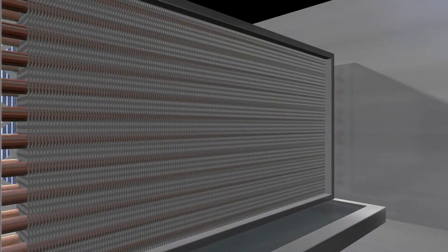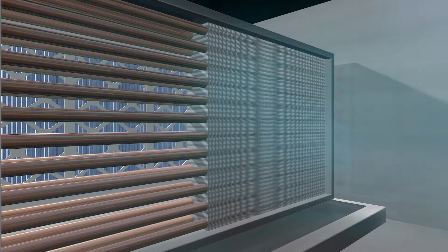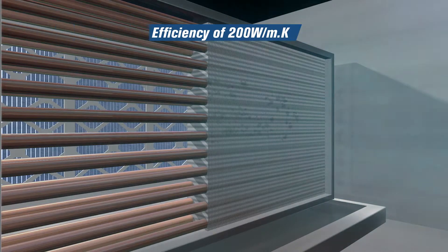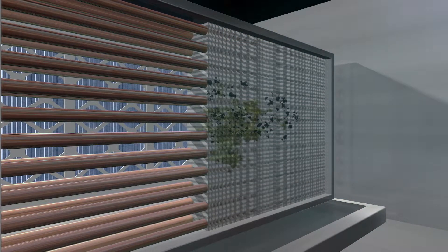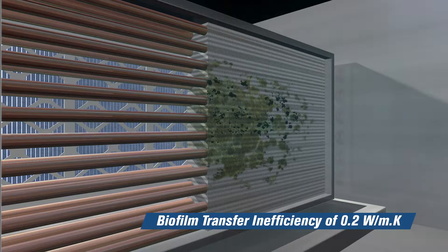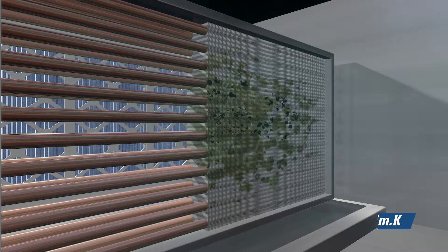The metal fins of the coil are typically made of aluminum that has a heat transfer efficiency of 200 watts per meter kelvin. Whereas, the biofilm that often covers the fins may be 0.2 watts per meter kelvin, or approximately 1,000 times less efficient.